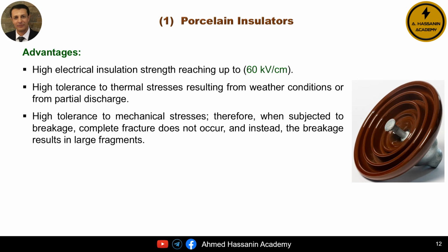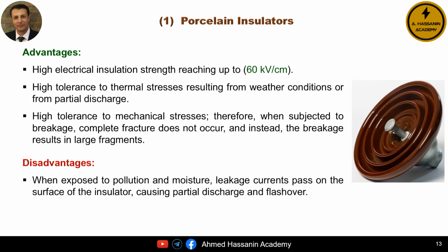Therefore, when a porcelain insulator breaks, it does not shatter completely but rather splits into large pieces. However, one of the disadvantages of porcelain insulators is that when they are exposed to pollution and in the presence of humidity, leakage currents will flow over their surface. This, of course, leads to partial discharge and may eventually cause a flashover.